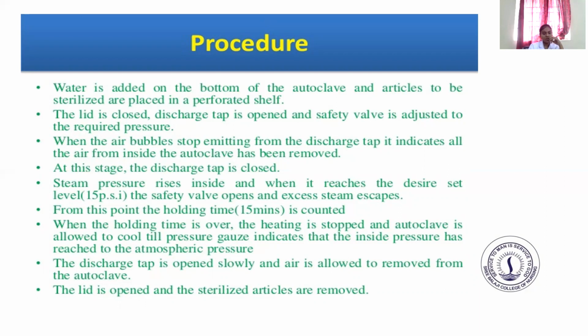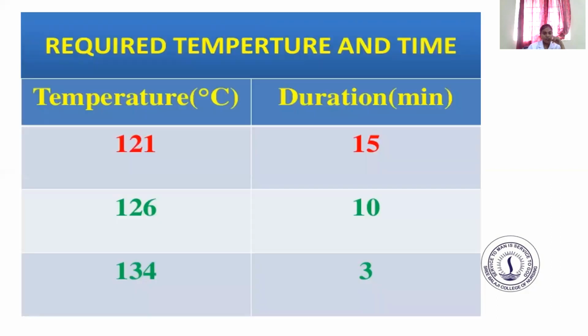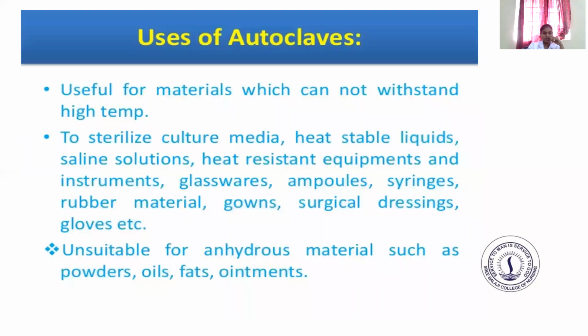When the holding time is over, the heating is stopped and the autoclave is allowed to cool. When the pressure gauge indicates that the inside pressure has reached atmospheric pressure, the discharge tap is opened slowly and air is allowed to enter the autoclave. The lid is opened and the sterilized articles are removed. Record temperature and time. Maintaining the correct time and temperature is a must. At 121 degrees centigrade the duration is 15 minutes. At 126 degrees centigrade the duration is 10 minutes. And at 134 degrees centigrade the duration is 3 minutes.